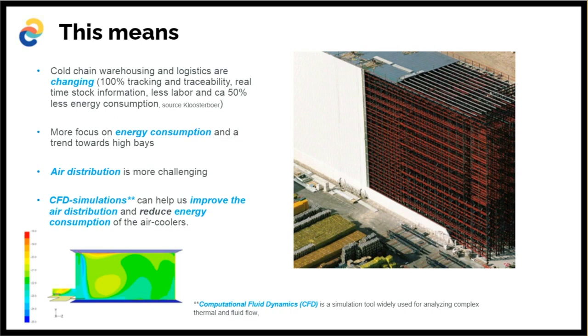And quickly, what is a high bay? You see a little picture of one being built there. They are around 40 meters high, 100 to 150 meters long, and 60 meters wide or so. They're quite high and big, and fully automatic. The point is, because of these high buildings, the air distribution is getting more and more difficult. You have to get all the air nicely distributed in these high bays. And therefore, there are CFD calculations and simulations that can improve this air distribution and where we can reduce the energy consumption.